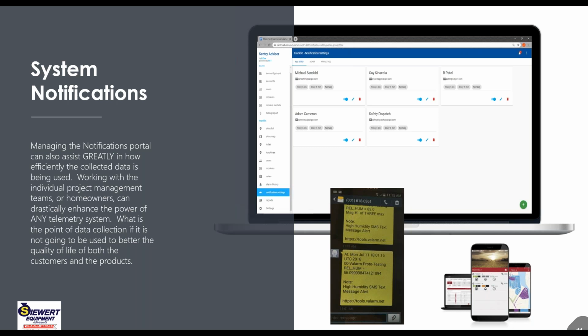Certain systems allow a little more flexibility in terms of delaying the alarms that come in to minimize nuisance events, because the last thing technicians, operators, and homeowners want is for somebody to show up at their house and potentially charge them money for something that wasn't really there. If an alarm happened because the homeowner was using a bathtub, a sink, and a shower all at the same time, that's expected - a momentary overflow of the system. We overwhelmed the capacity of the pump, but the pump will play catch up, evacuate the fluid, and we're done. There was no need for a call there. That's why certain systems allow delays to be configured.